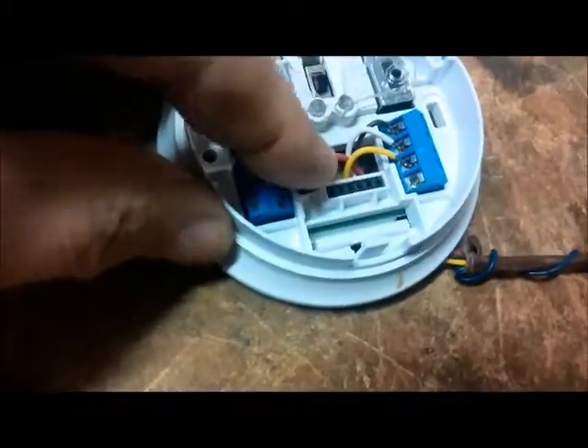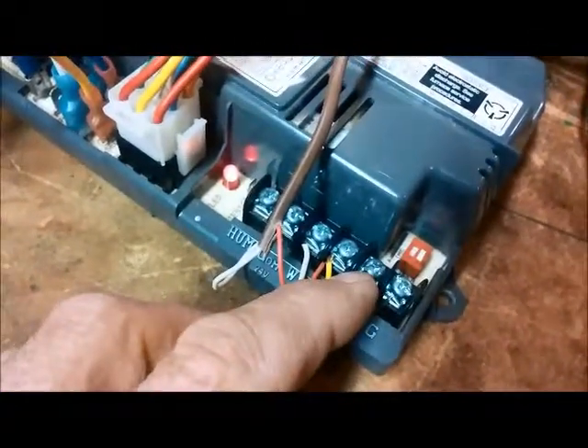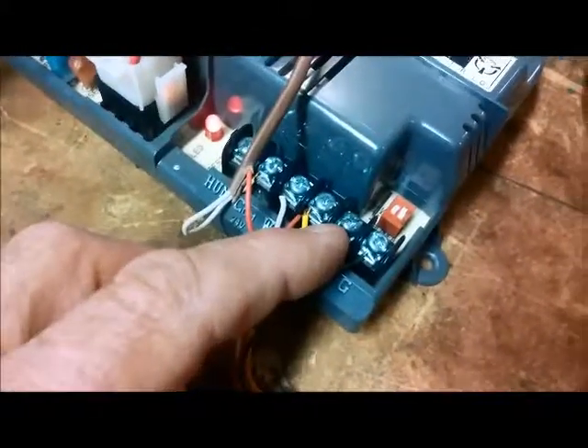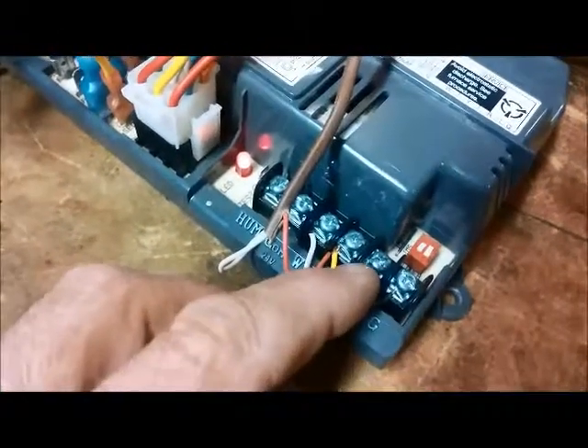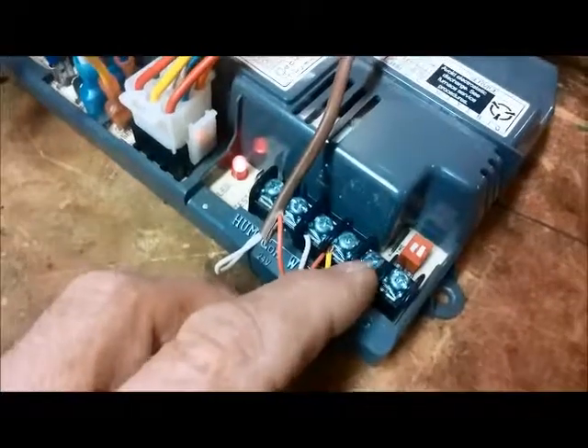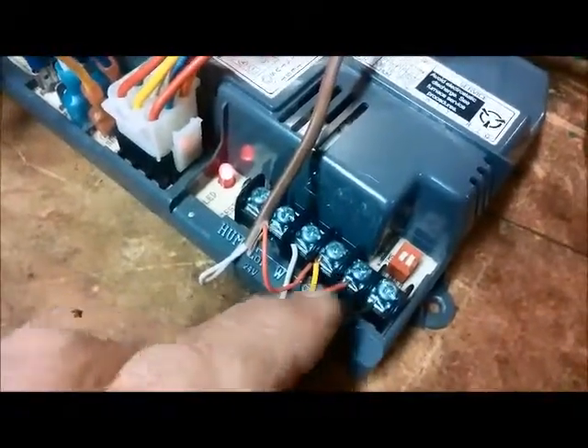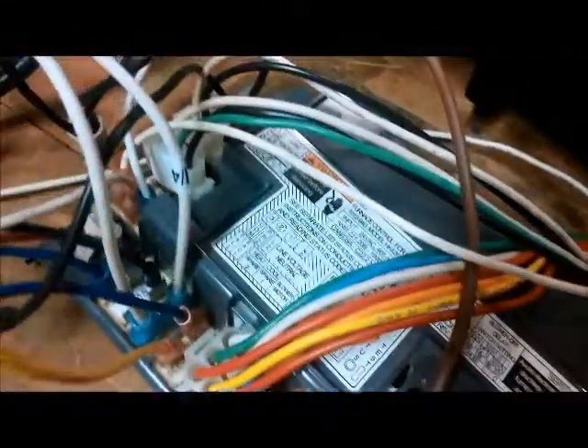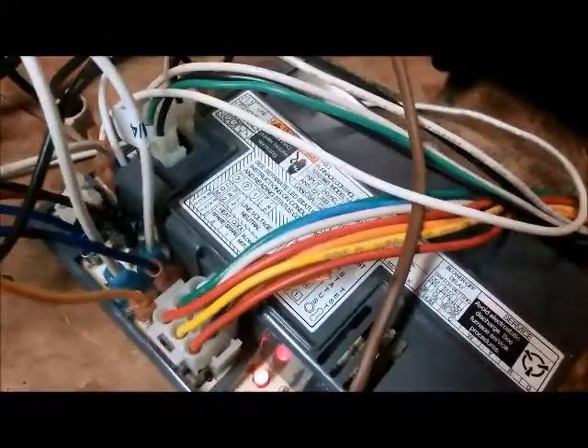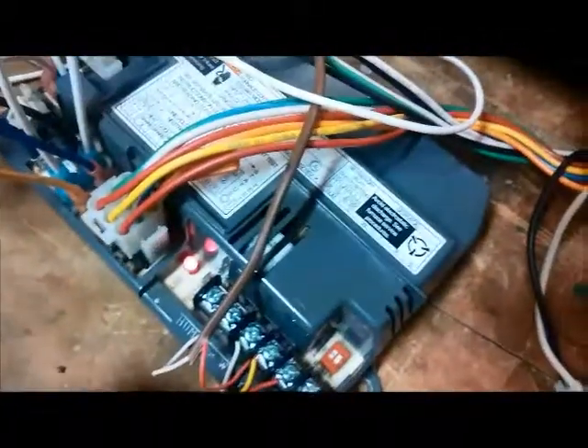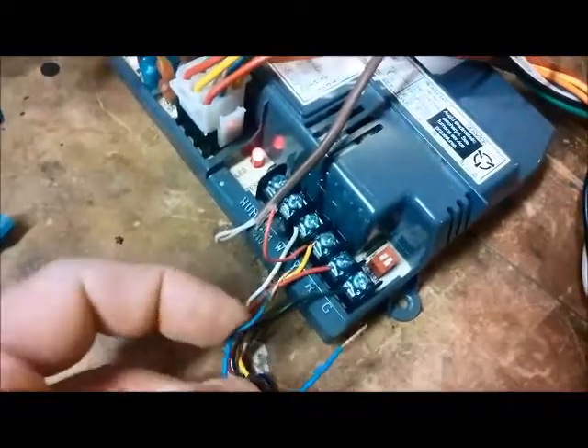R is power, and all the thermostat does, say the thermostat does nothing more than take the 24 volt power from the R that is sitting in it waiting to go somewhere. So you turn the fan on at the thermostat, it's going to attach the R to the G. In other words, letting that 24 volt power go from the stat back down the G wire, and that's going to power up a relay in here, which is going to close and send 110 volts to the blower motor. So we could do that by jumping R and G together here manually to see if our fan control on the stat is working, or we could just turn the fan on at the stat and then our blower motor will run.